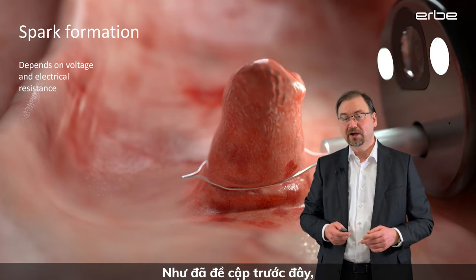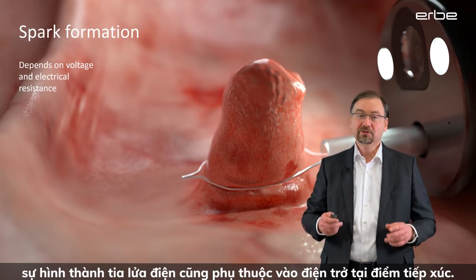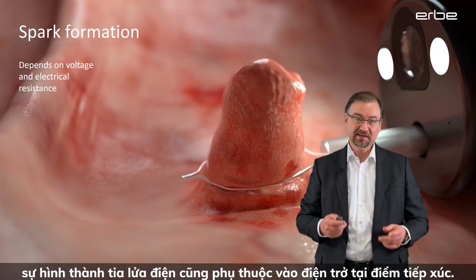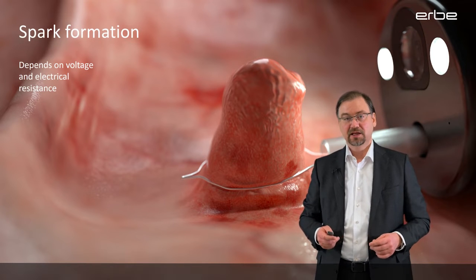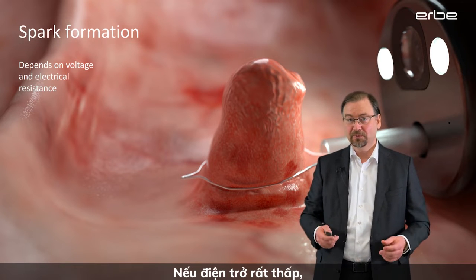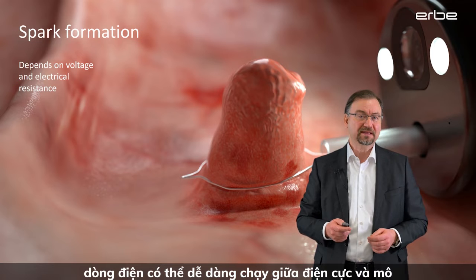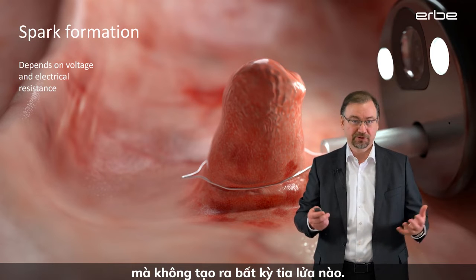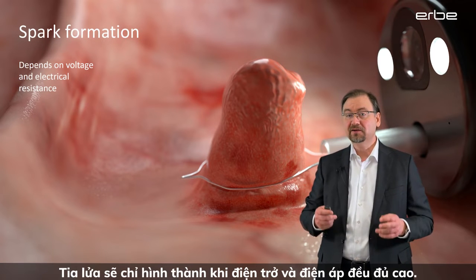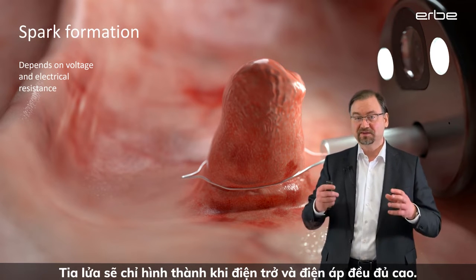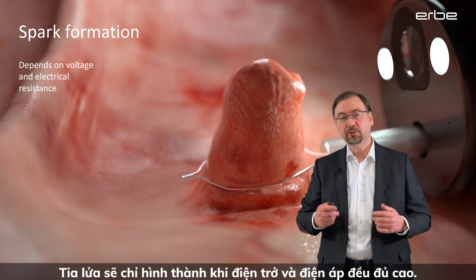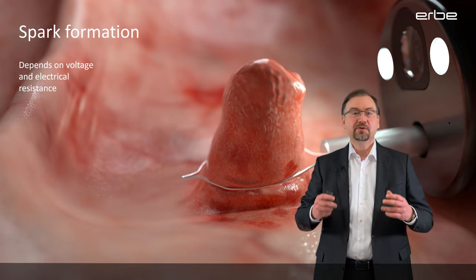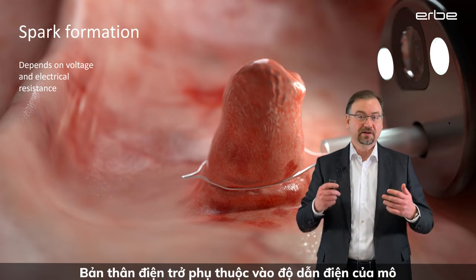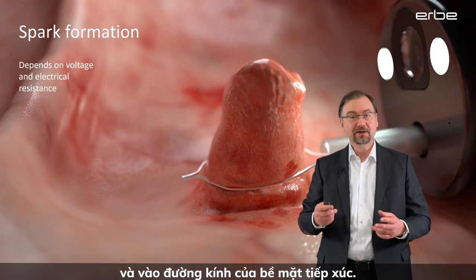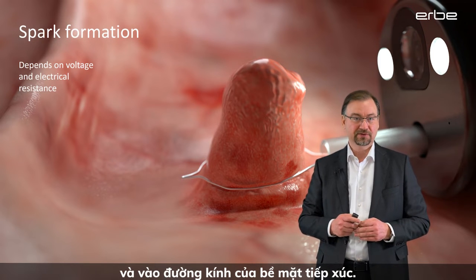As I mentioned before, the spark formation also depends on the electric resistance at the point of contact. If the resistance is very low, the current can easily flow between the electrode and the tissue without producing any spark. Sparks will only develop when the resistance and the voltage are both high enough. The resistance itself depends on the conductivity of the tissue and on the diameter of the contact surface.